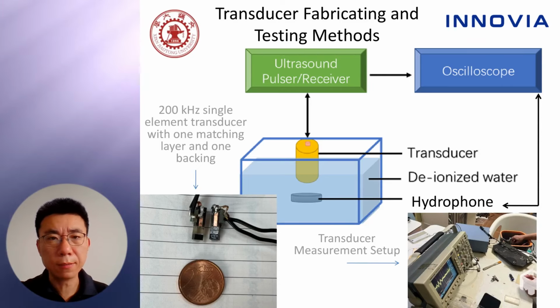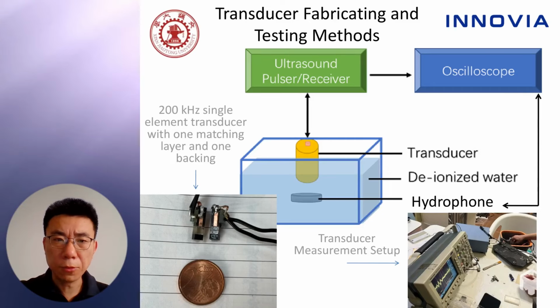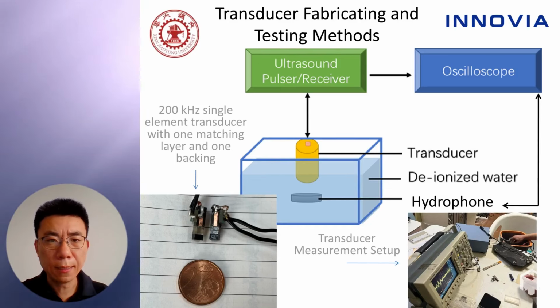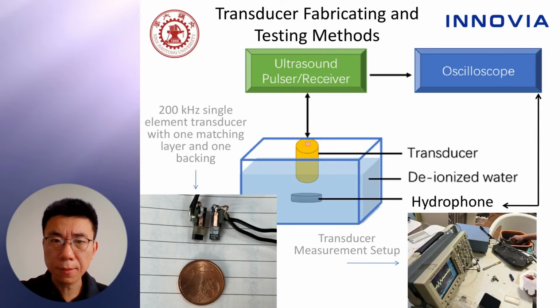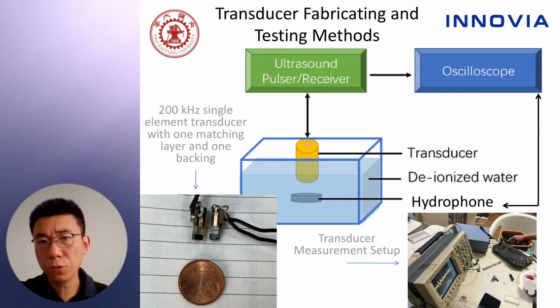Let's look at the transducer fabricating and testing methods. First of all, crystals of different poling conditions will be manufactured into single element transducers corresponding to 200 kilohertz, with a typical application of breast cancer treatment. They have 1 matching layer and 1 backing. Those transducers, together with a hydrophone, we put under water in the water tank, 20 millimeters apart. The transducers would be connected to an Olympus ultrasound pulser receiver, which is then connected to an oscilloscope. The oscilloscope will generate the waveform that we needed for measurement of minus 6 dB bandwidth and sensitivity.